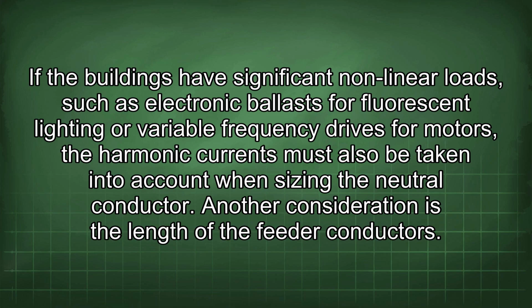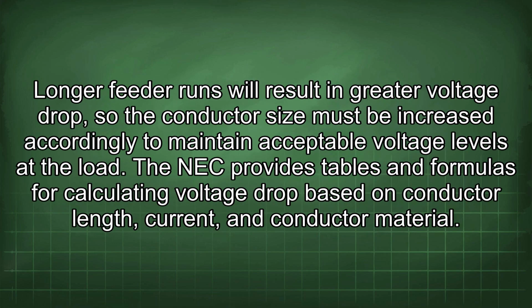Another consideration is the length of the feeder conductors. Longer feeder runs will result in greater voltage drop, so the conductor size must be increased accordingly to maintain acceptable voltage levels at the load. The NEC provides tables and formulas for calculating voltage drop based on conductor length, current, and conductor material.